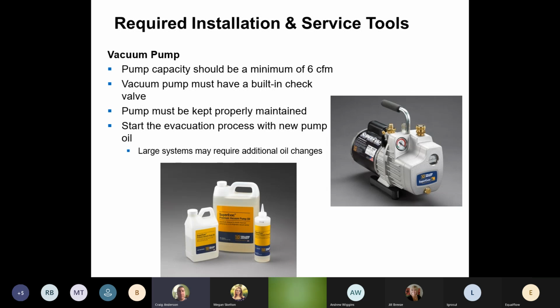New systems aren't too bad, but when we're doing a retrofit, when we're doing something that's already had Freon through the system and has been open, there's a lot more moisture, especially if we're vacuuming the outdoor unit. So those units are going to take a lot longer to vacuum. If you've got clean oil, then that's going to help you get your vacuum a little quicker. So maintain your oil.